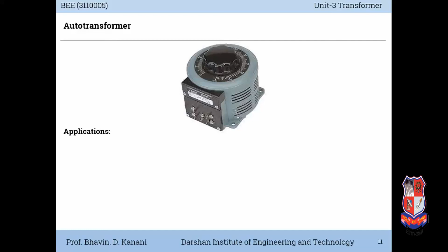Compensating voltage drops by boosting supply voltage in distribution systems, that means as a voltage booster. Auto transformers with a number of tappings are used for starting induction and synchronous motors. Auto transformer is used as variac in laboratories or where continuous variable or broad ranges are required. The auto transformer is also used as a balance coil to give a neutral in a 3-wire AC distribution system.